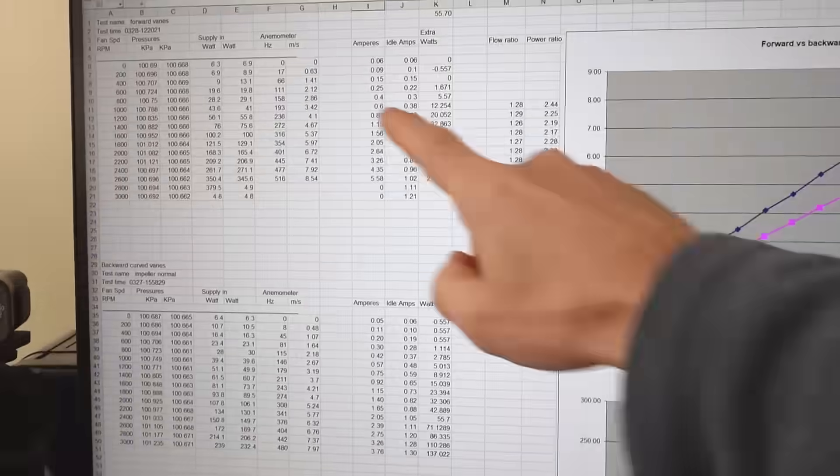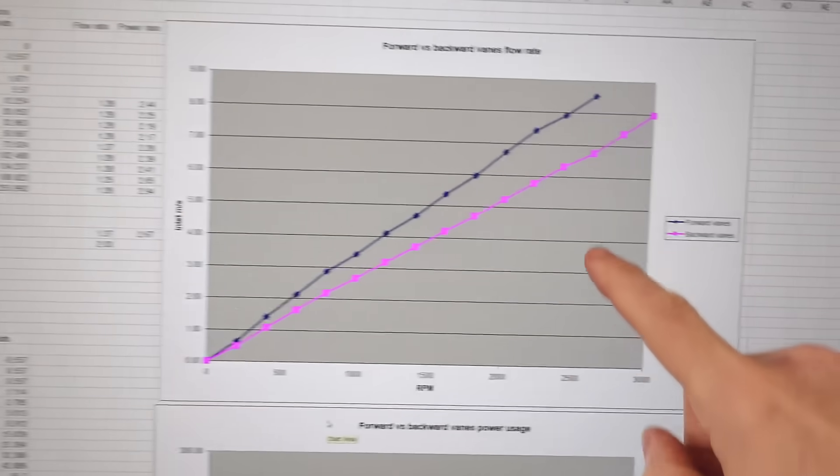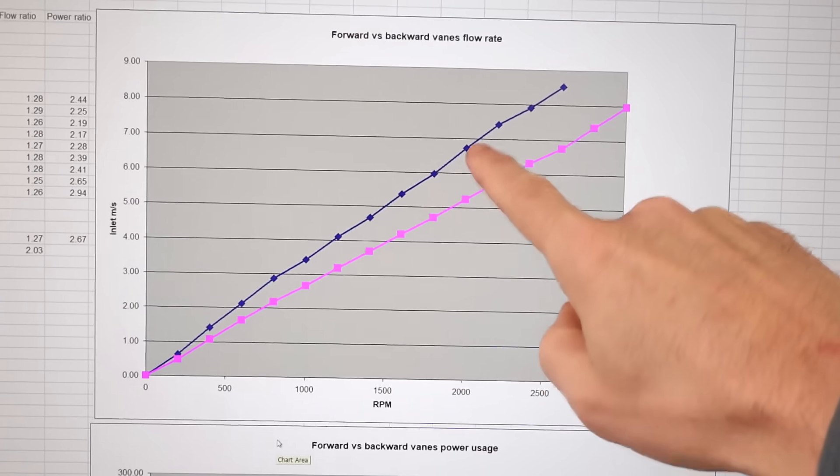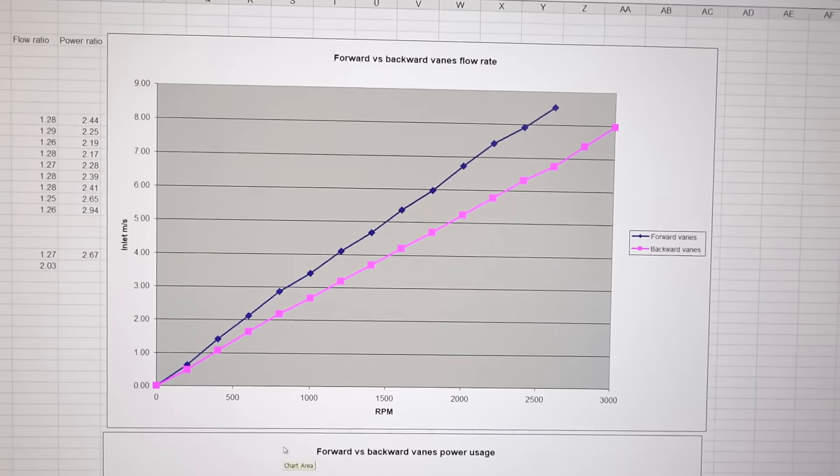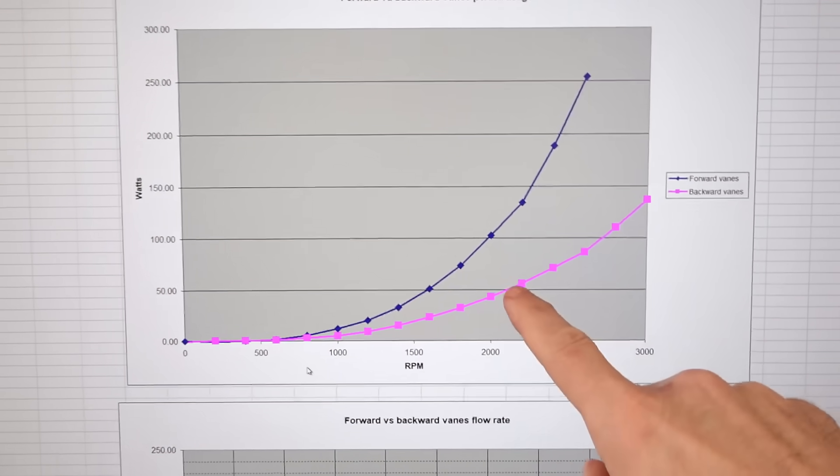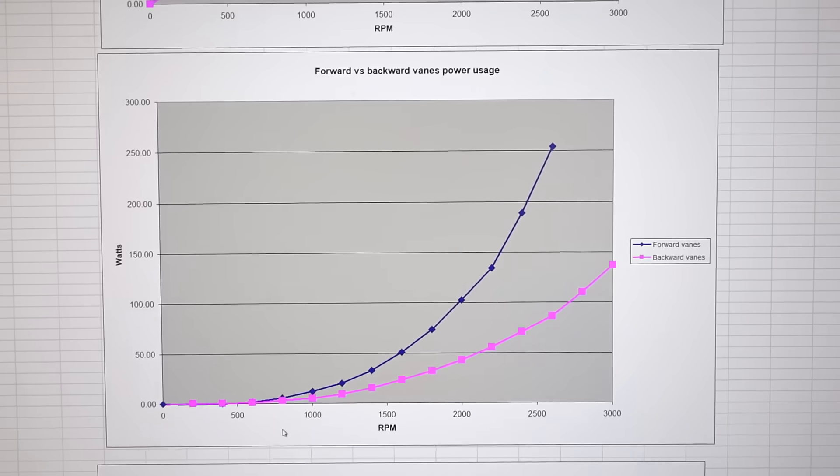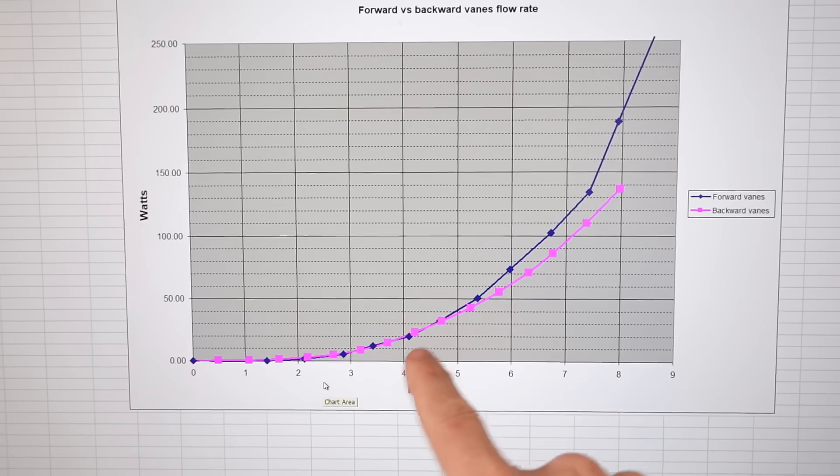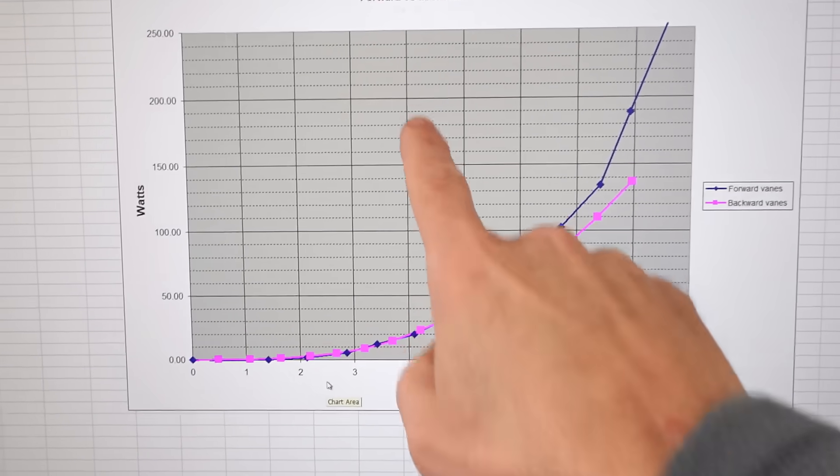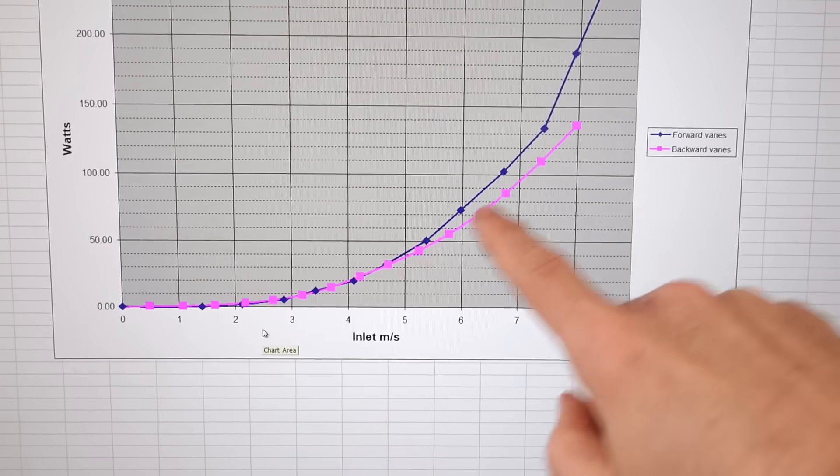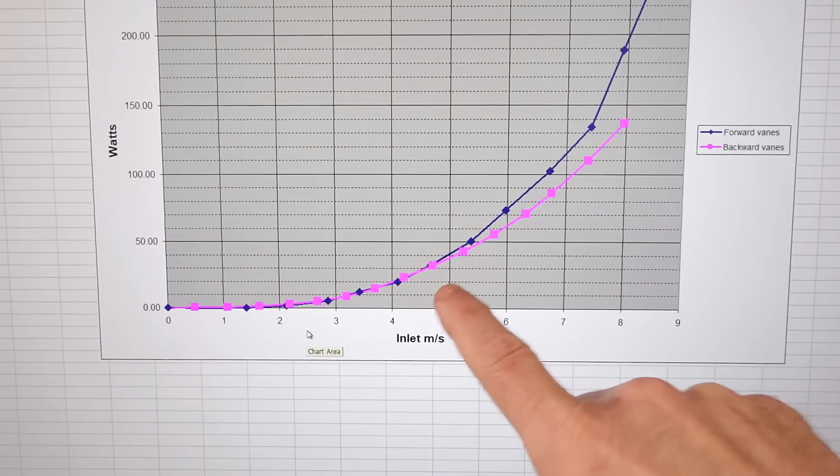Now comparing forward facing versus backward facing vanes: the flow rate is considerably higher by about 26%, but if we look at the power consumption as a function of RPM, it's dramatically higher, more than double. But then if we plot the power consumption versus flow rate, it's actually not that far apart.